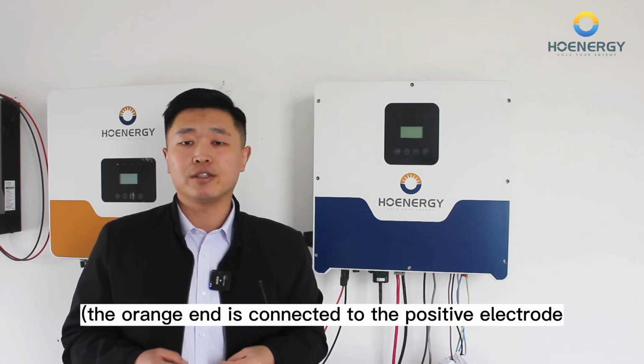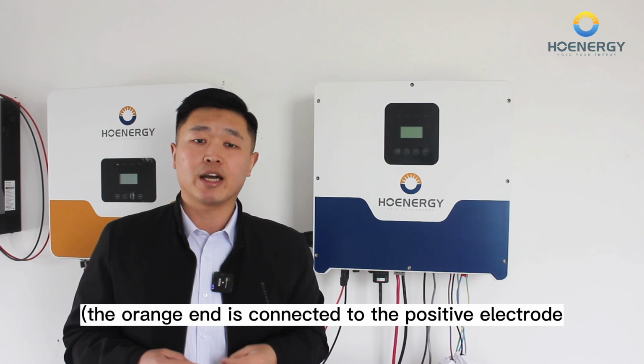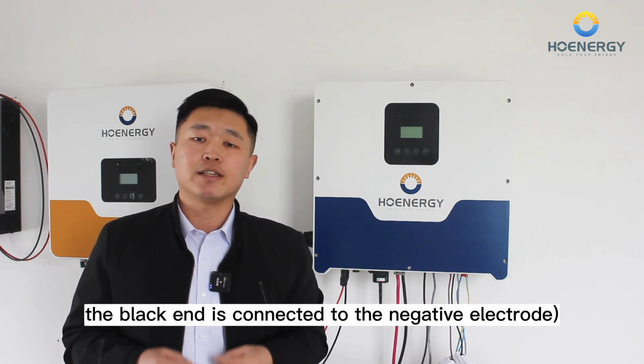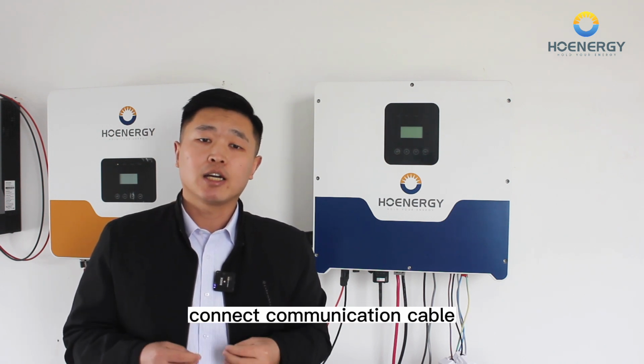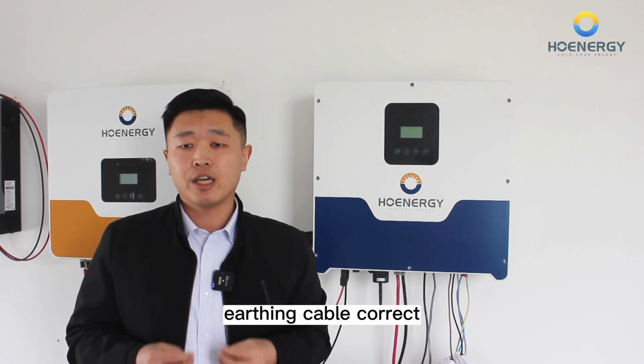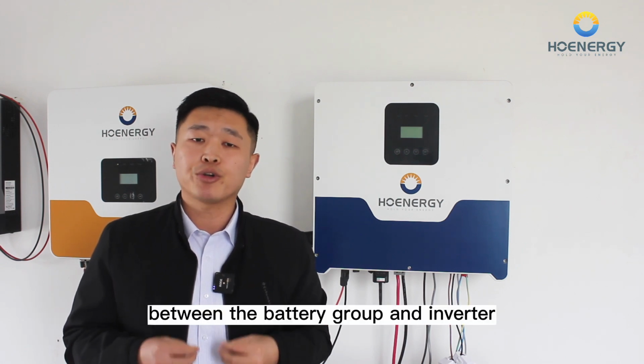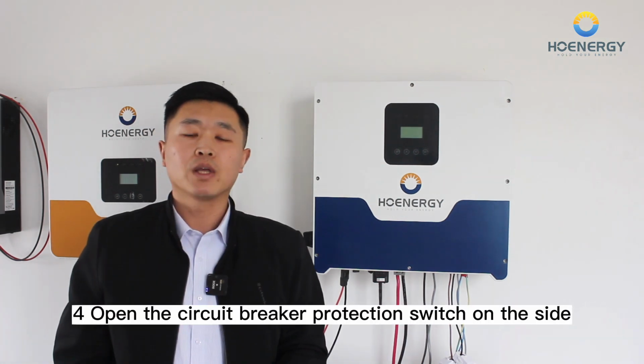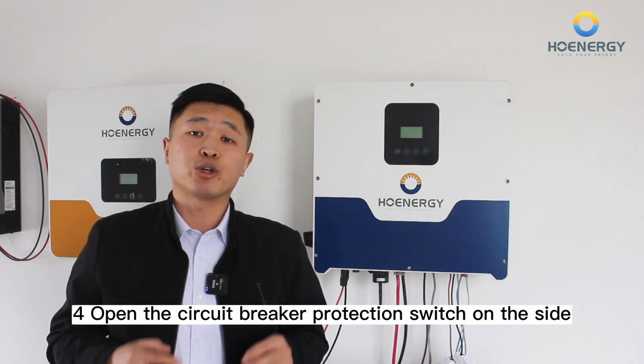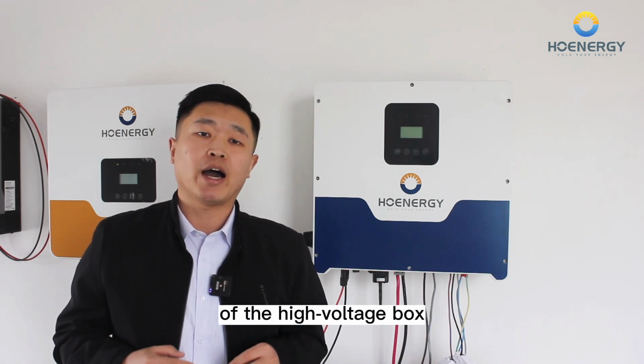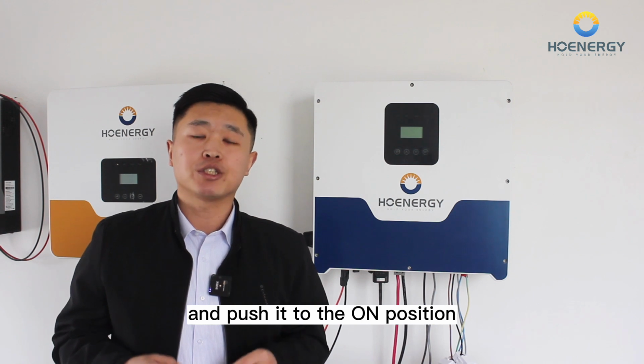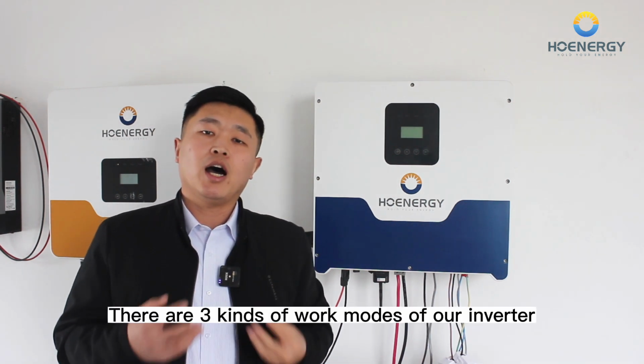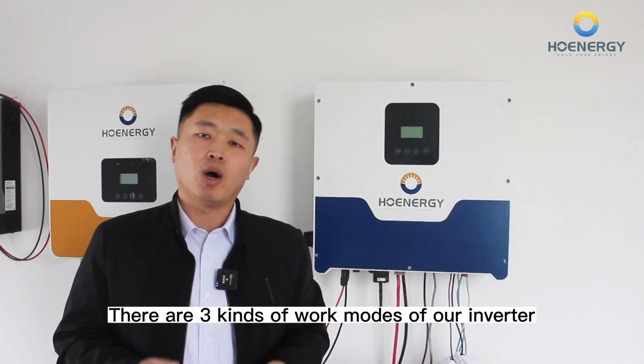The orange end is connected to the positive electrode. The black end is connected to the negative electrode. Connect communication cable, earthing cable correctly between the battery group and the inverter. 4. Open the circuit breaker protection switch on the side of the high voltage box and push it to the on position. There are 3 kinds of work modes of our inverter.